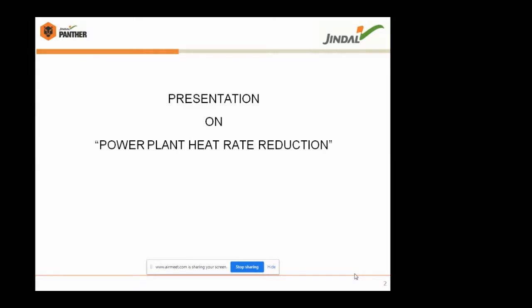Before starting this, let me tell you, in our plant the steel load is very variable. The variation of load is in the range of 0 to 180 megawatt because of the electric arc furnace. Due to that reason, we are regulating our load or generation to control the unscheduled power, meeting the requirement of the steel plant.